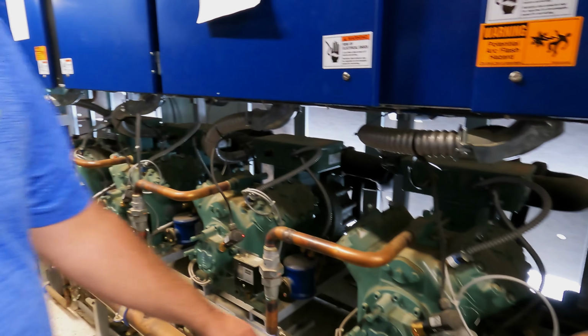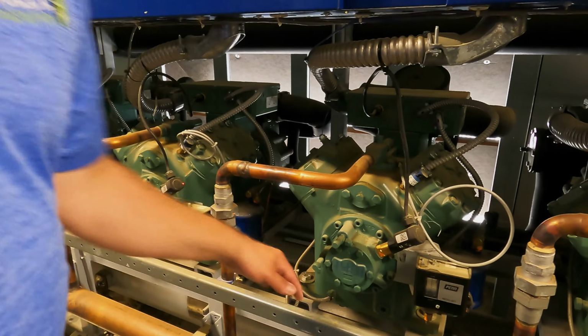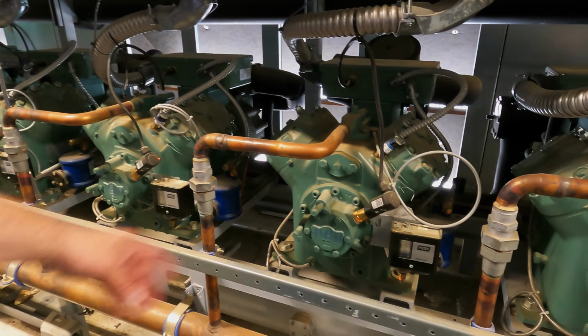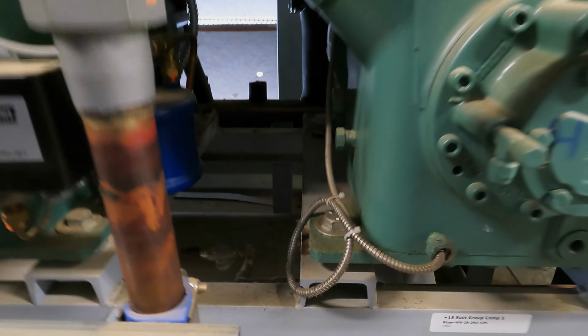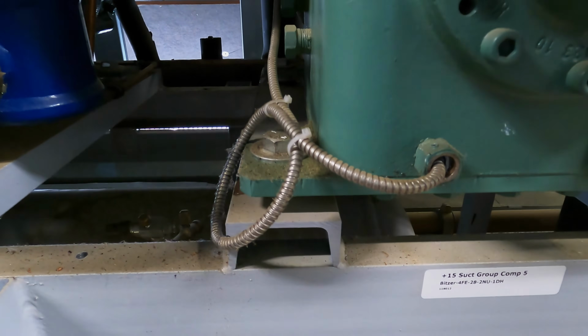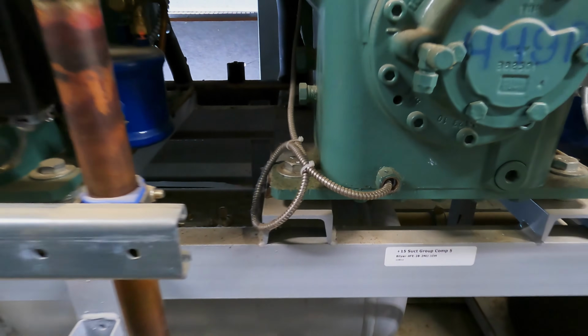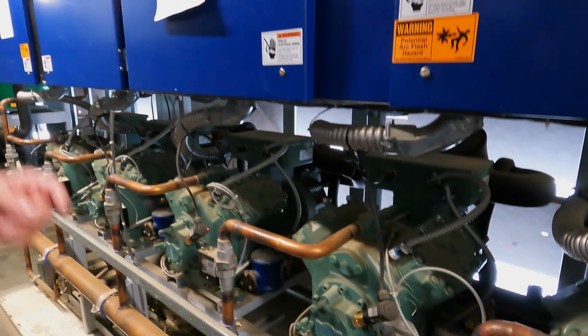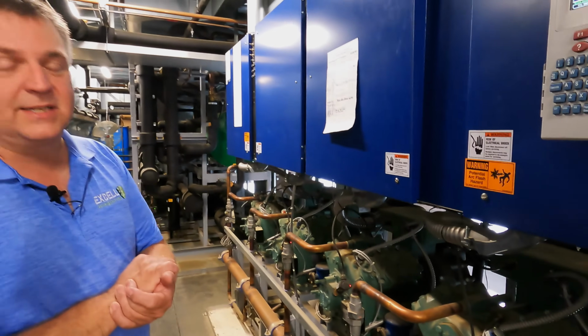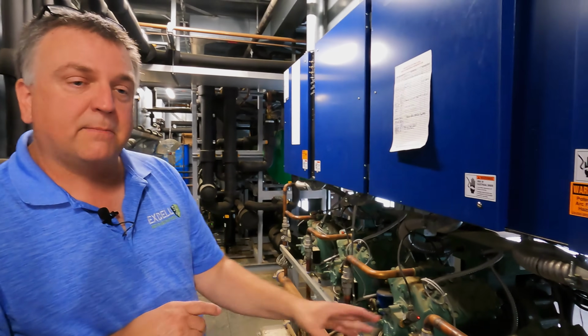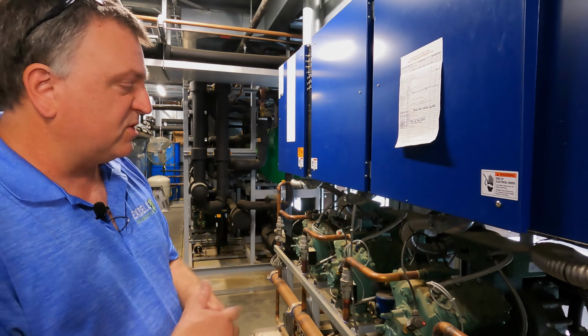We also have a crankcase heater. When the compressor is in this off mode, it keeps the bottom of that warm to keep any refrigerant in there from condensing to a liquid. And once you turn it on, if it's in a liquid state, it's going to bang like hell, because why? You can't compress a liquid. So that heater keeps that bay warm in order to keep it in a vapor state.